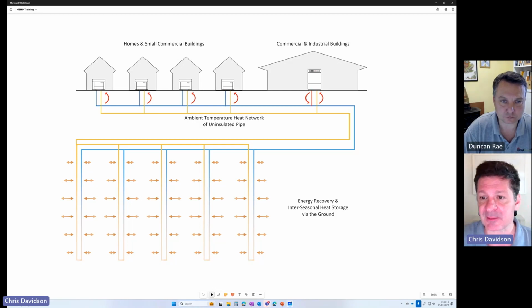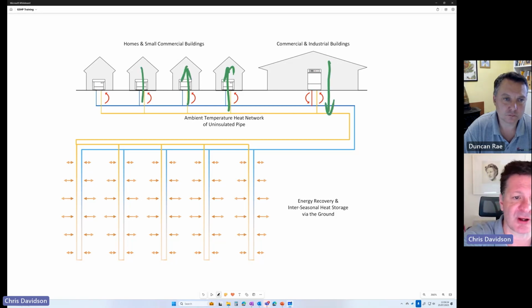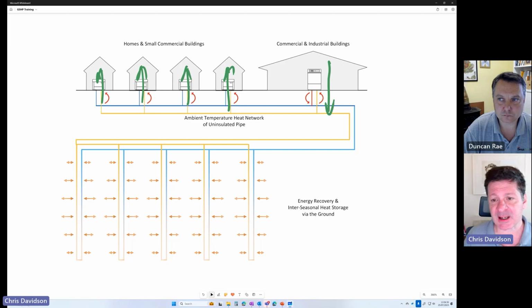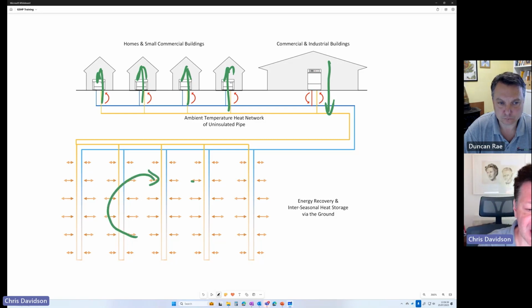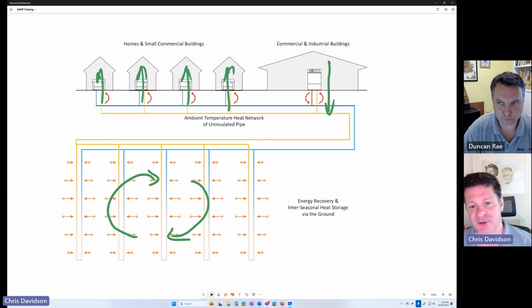However, if you do get that compulsion, then putting that heat into the network and then taking it out, utilising other types of building, is a very, very effective way of doing ground source and balancing that ground loop temperature out, improving the efficiency of the cooling and the efficiency of the heating. And the real magic, of course, is that interseasonal energy recovery I talked about earlier on. Sorry.